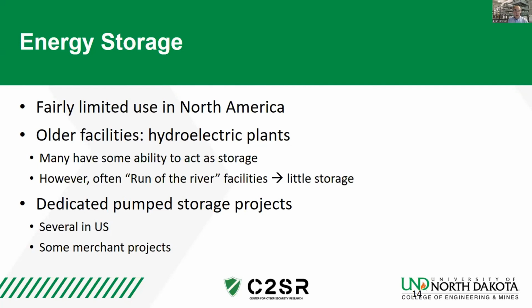Some of the older systems, like Banks Lake at Grand Coulee Dam in north central Washington, were set up so they could only start the pumps once a day. The thermal shock from starting those pumps meant they couldn't do repeated starts. About 15 years ago they refurbished those for more operational flexibility. But when they're pumping, they pretty much just pump at one rate. When generating, they can control them like any other generator.